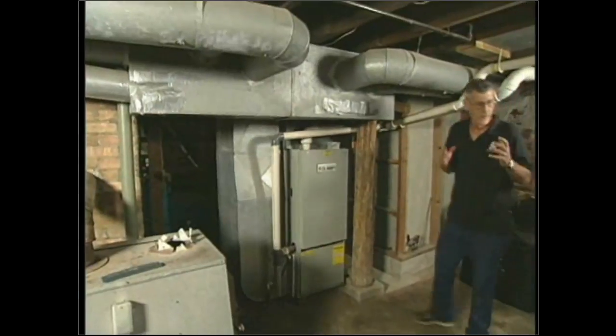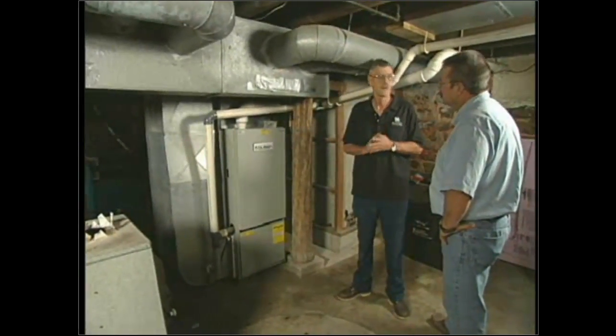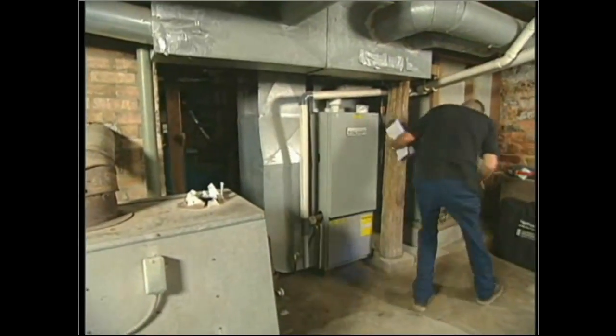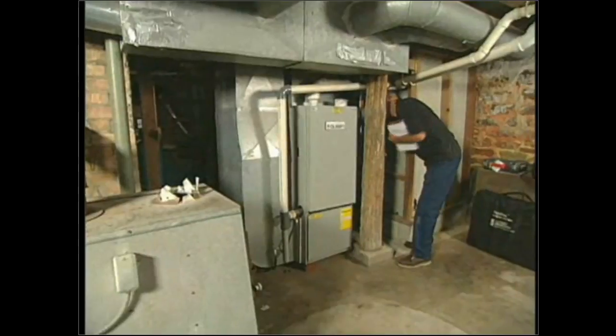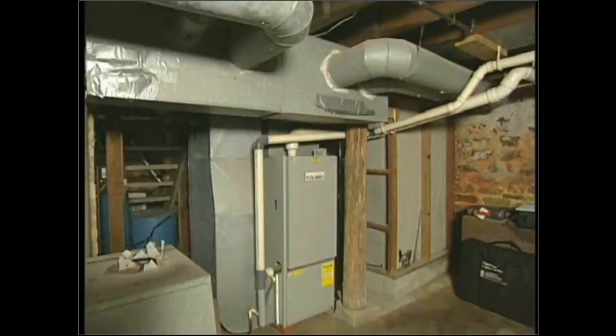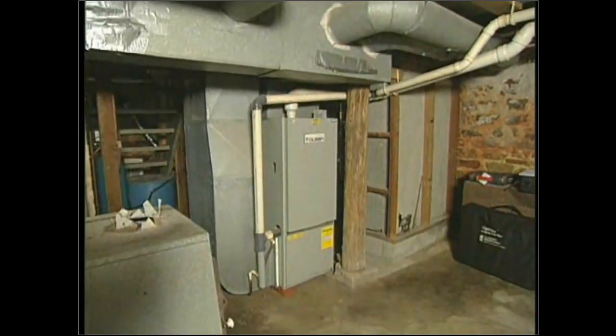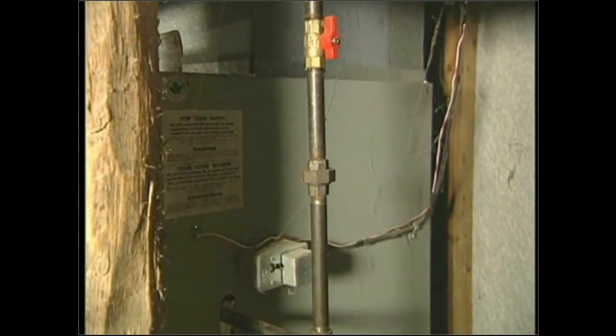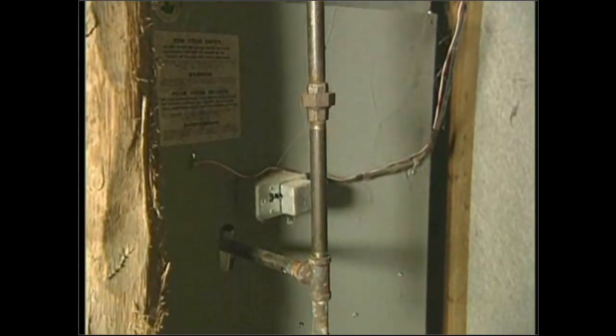After meeting with the homeowner, I come down and take a look at the heating system first for a visual inspection. Before I even open the cabinet, I'm looking around the base of the unit to see if there's any moisture on the ground from condensate — this is a 90-plus condensating furnace. If there are any concerns with condensation leaks, I'll be able to see them on the concrete. I'll also visually locate the gas valve and inspect the gas line.